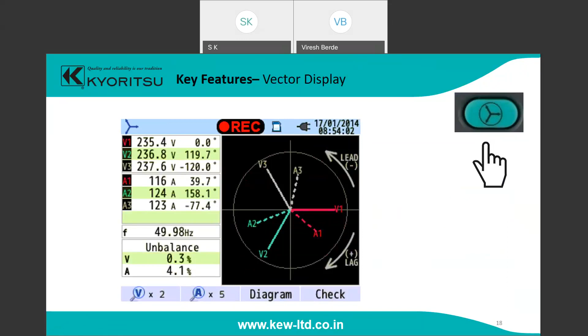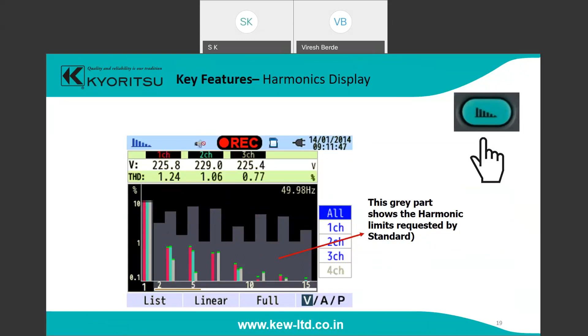There's a harmonics button also. Press the harmonic button and the display directly shows your system's harmonics. In this photo, it basically shows the third, fifth, and seventh harmonics. This gray color shows the limits as per standards, and R means your wave phase harmonics are higher than the Y phase harmonics. So you can directly display and read out the harmonics.